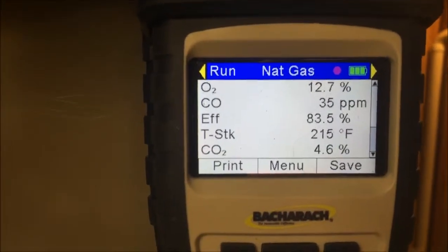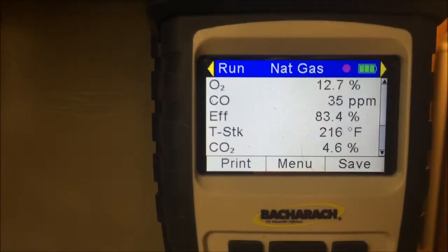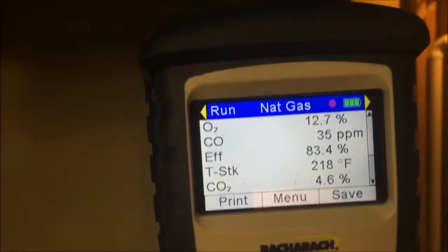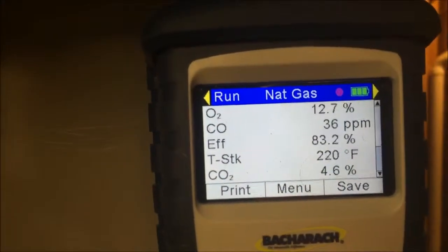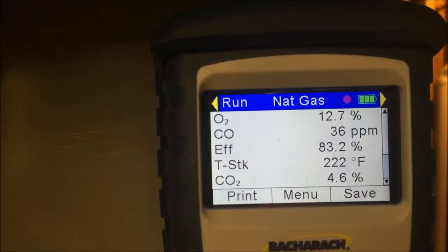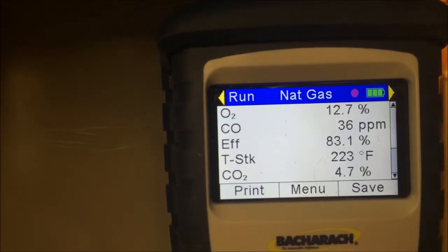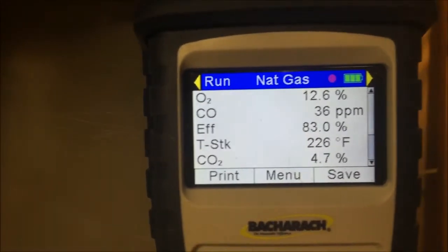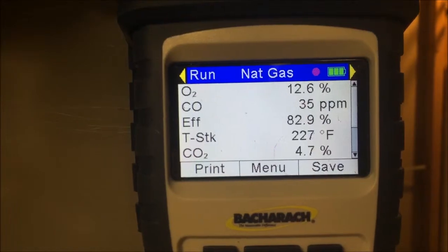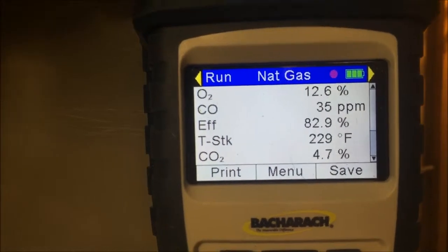If you got a modulating furnace or something that adjusts itself all the time, you got to make sure you have the gas valve running at 100%. If you don't, you'll be trying to tune this in to a gas valve that's only putting in maybe 60% of its capacity, and it's silly to do that.